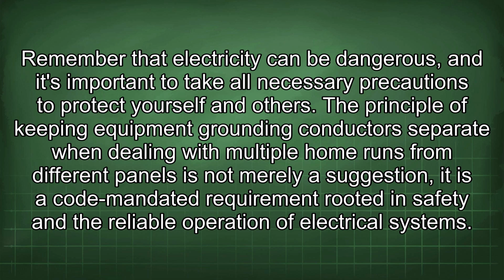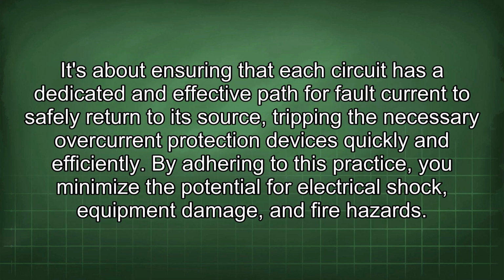The principle of keeping equipment grounding conductors separate when dealing with multiple home runs from different panels is not merely a suggestion, it is a code-mandated requirement rooted in safety and the reliable operation of electrical systems. It's about ensuring that each circuit has a dedicated and effective path for fault current to safely return to its source, tripping the necessary overcurrent protection devices quickly and efficiently. By adhering to this practice, you minimize the potential for electrical shock, equipment damage, and fire hazards.